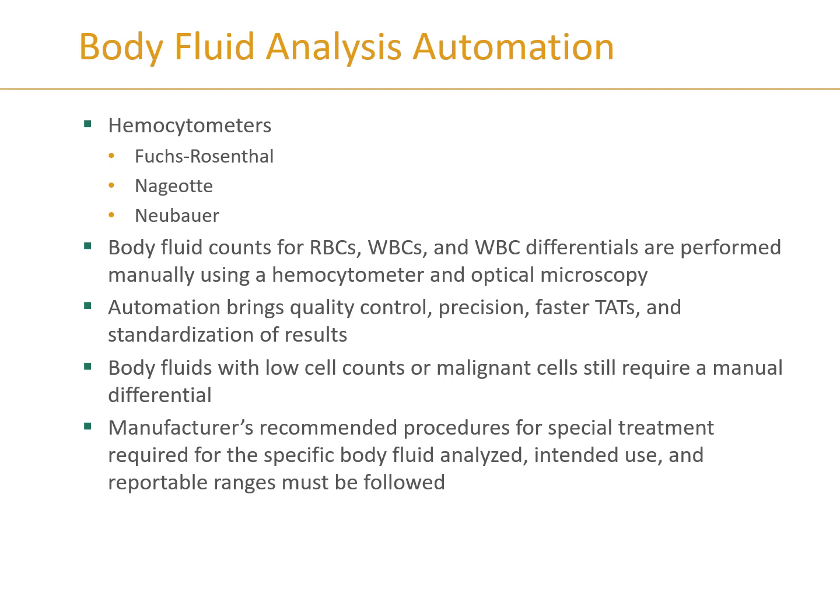For manual body fluid testing, a hemocytometer is used. Automated testing speeds up the process, performs quality control and precision checks, and brings standardization that reduces variability between technicians. If cell counts are very low or malignant cells are present, a manual differential is still required, including cytocentrifuge spin slides. Anything potentially malignant should be confirmed, so that extra step is not a significant hardship.